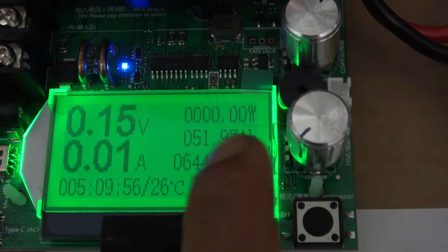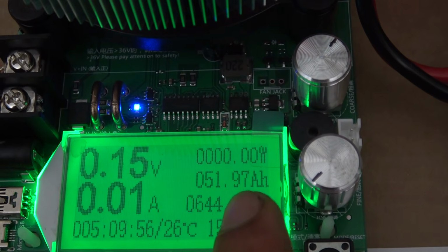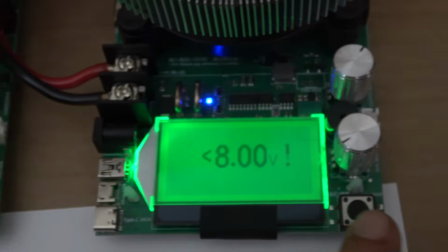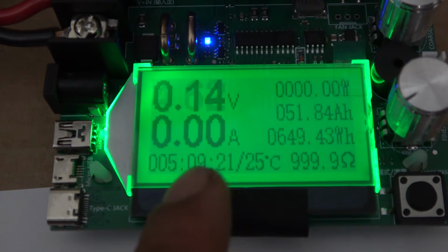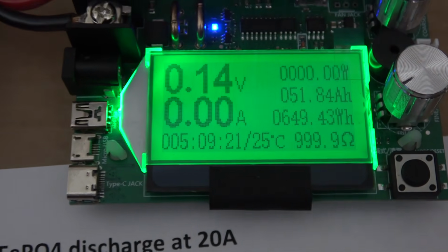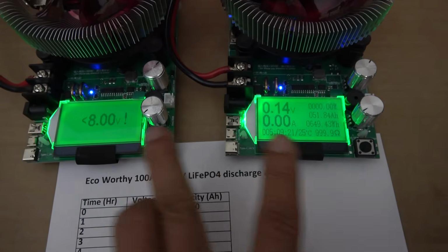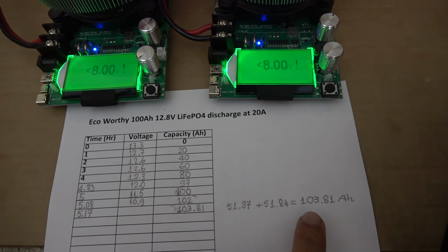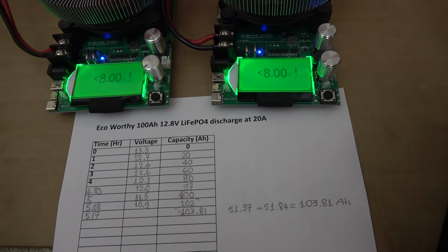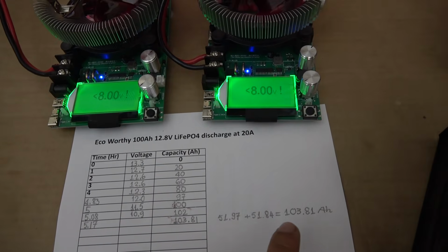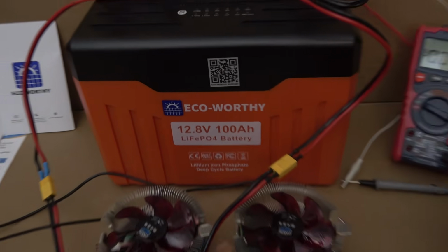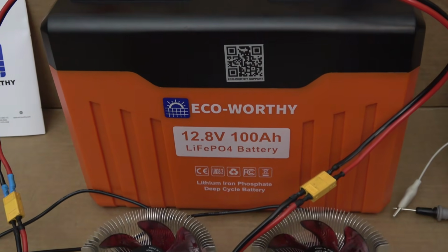One on the left, 51.97 amp hour. The one on the right, 51.84 amp hour. So the total capacity is 103.81 amp hour. That's a little bit more than the rated 100 amp hour from eco-worthy, so that's awesome.